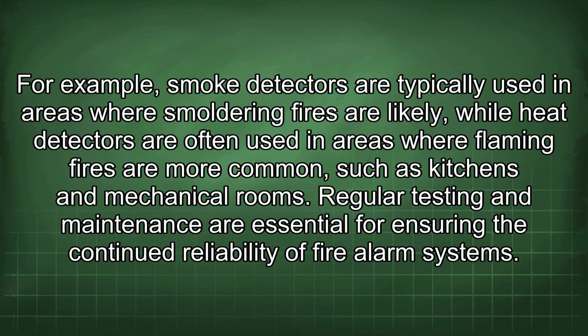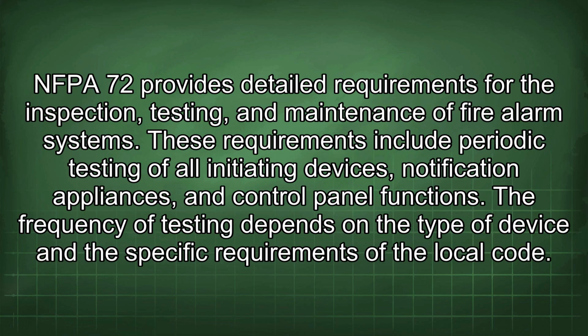For example, smoke detectors are typically used in areas where smoldering fires are likely, while heat detectors are often used in areas where flaming fires are more common, such as kitchens and mechanical rooms. Regular testing and maintenance are essential for ensuring the continued reliability of fire alarm systems. NFPA 72 provides detailed requirements for the inspection, testing, and maintenance of fire alarm systems. These requirements include periodic testing of all initiating devices, notification appliances, and control panel functions.